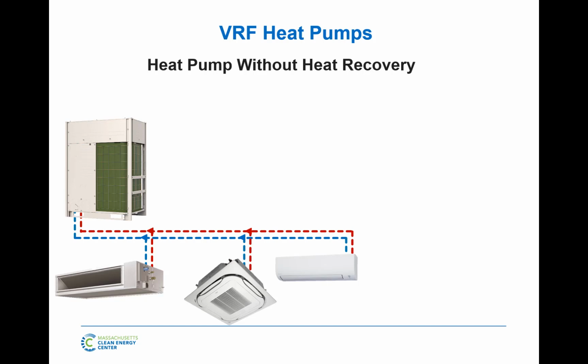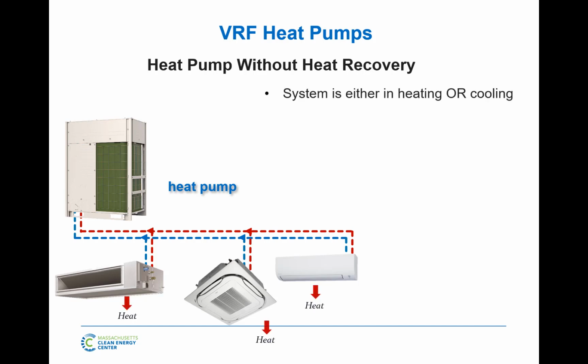Okay, if there's two technical things you remember today about VRF, it's the two types of VRF systems, which is heat pump and heat recovery. One's also called a switchover system, and the heat recovery is also called the simultaneous heating and cooling. Let's start with the first one, the basic one, which is the two-pipe heat pump switchover system. What that means is this machine out there is either in cooling or it's in heating mode.